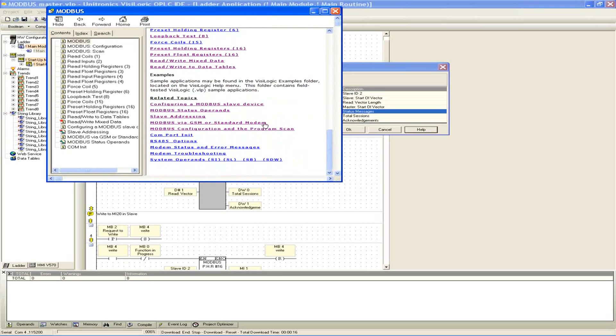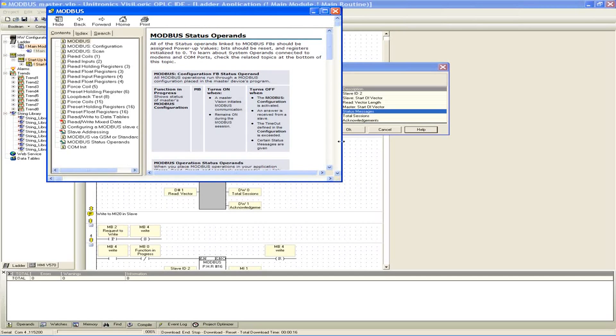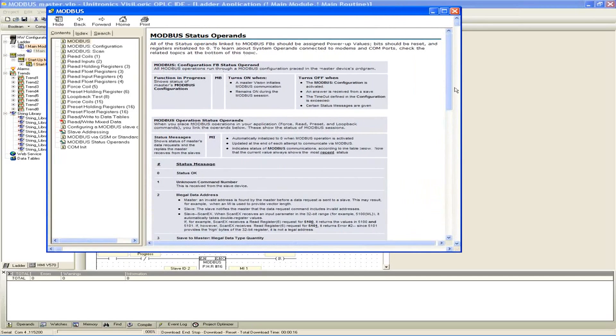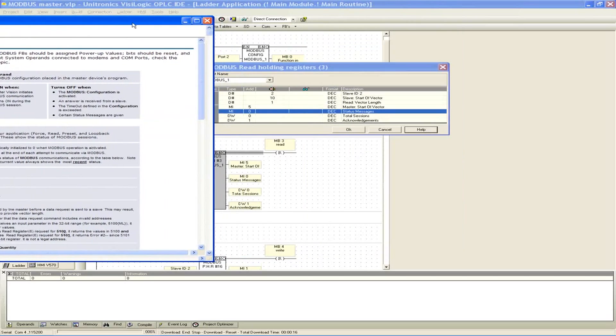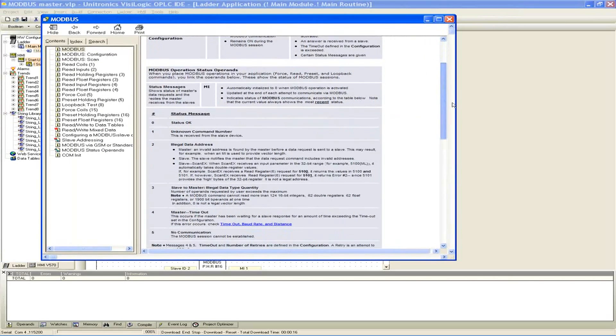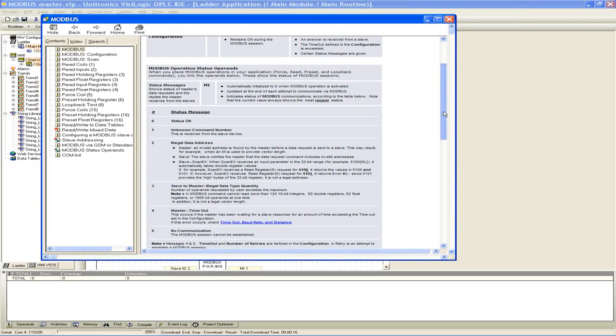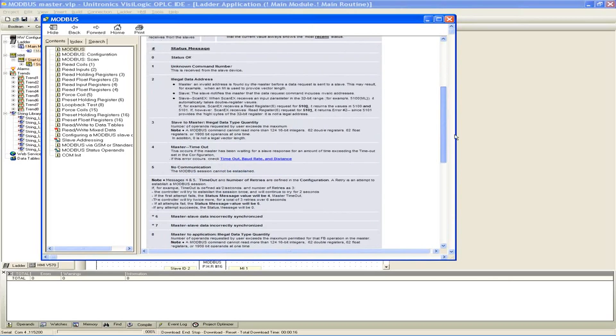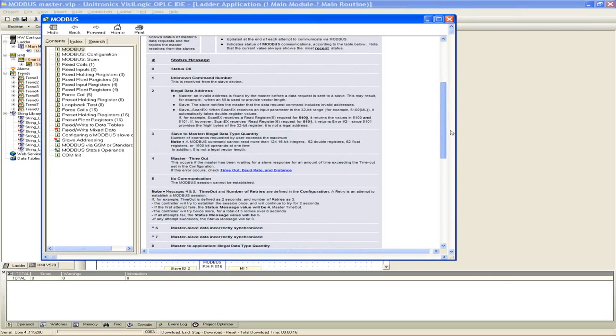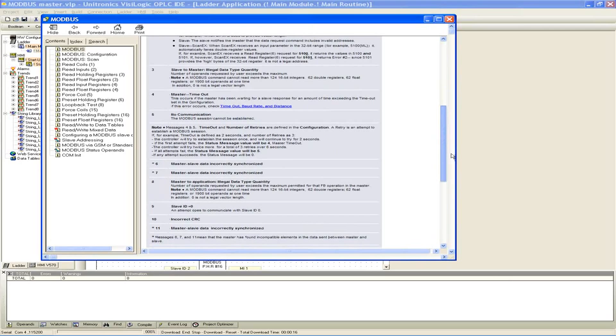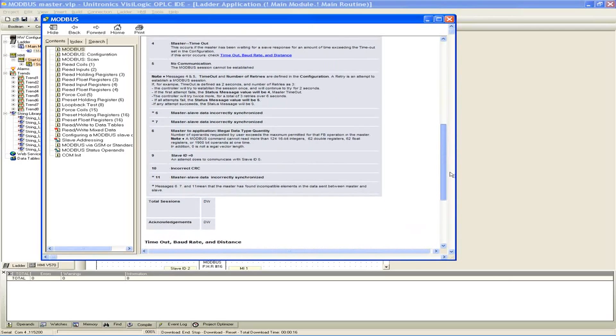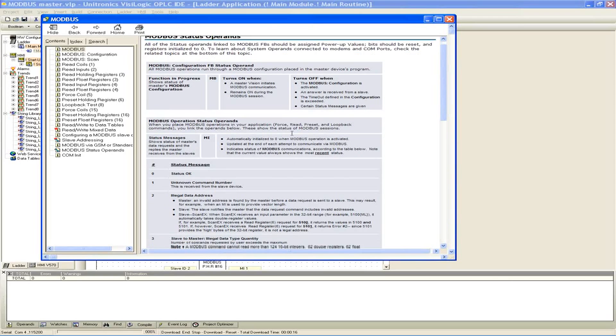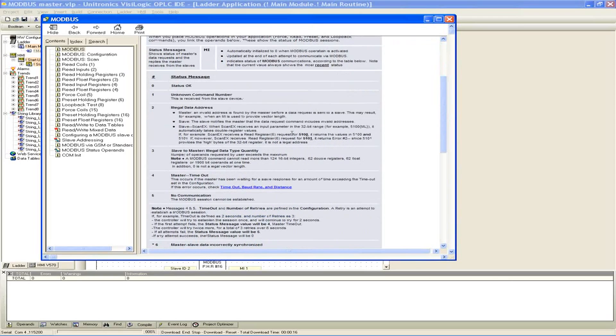And what I'm looking for is our Modbus status operands. Let me just make this a little bit larger. So the value that we have in MI0 in this case, if you have a 0 in MI0, it means everything is good. Your status is okay. Some possible numbers you could be getting in there is a 0, 1, 2, 3. It really just helps you try to debug and troubleshoot your application if your master is timing out or you have no communications or an illegal address. Any of those Modbus status messages will be placed in the number. And then you can see the equivalent number and a description of the error from the help file that shows your Modbus status operand. So you can always open up the help file and be able to go in and see what those statuses correlate to.